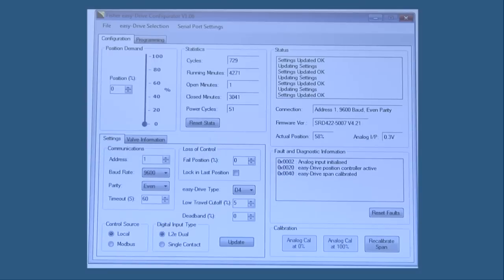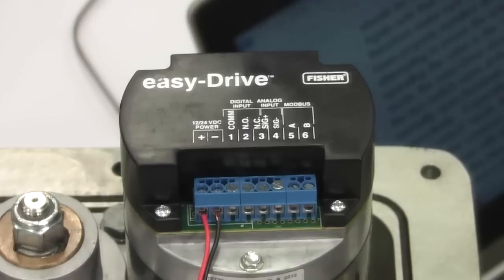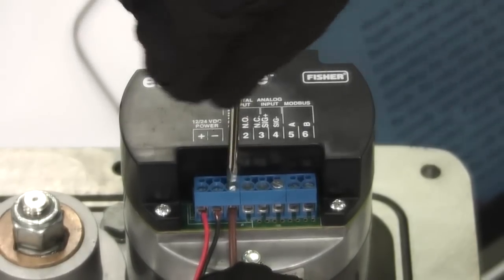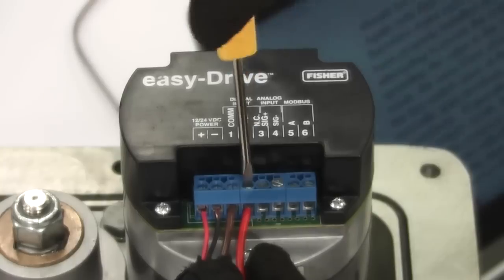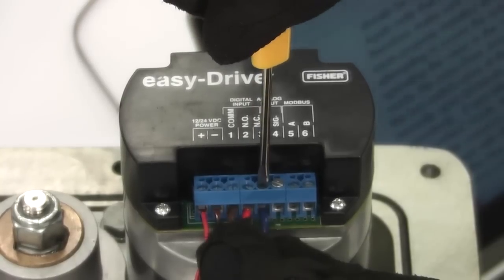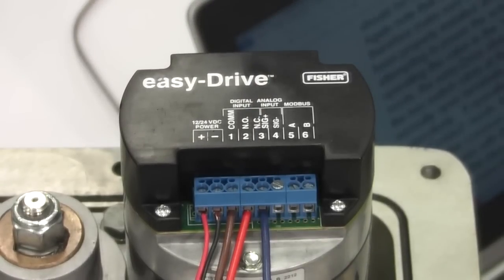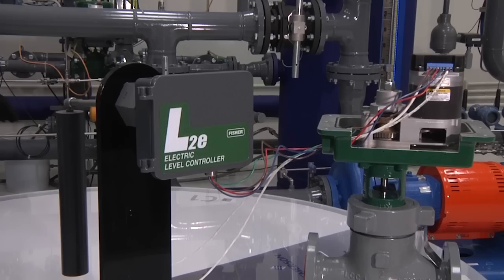The second type of on-off mode is the L2E dual dry contact mode. This uses the common, normally open, and normally closed terminals, which are terminals one, two, and three, respectively. We will use the Fisher L2E electric level controller to demonstrate this connection.